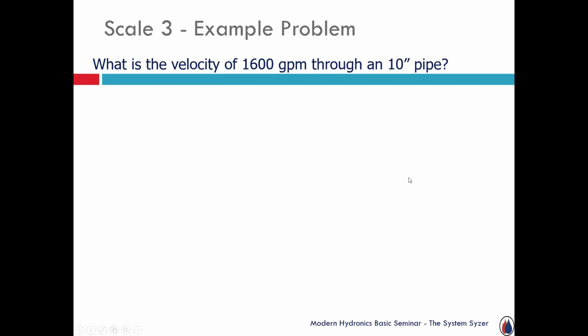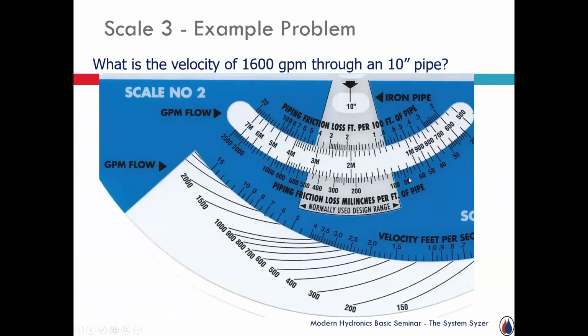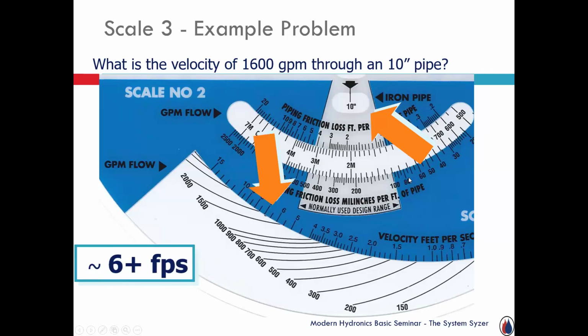The next pipe size up becomes 10-inch. So what's the velocity of that same flow through 10-inch pipe? Same exercise, 1,600 GPM. Where does it intersect? Just about 6 feet per second, plus or minus. It's a good selection. So again, that's just a way of using scale 3.